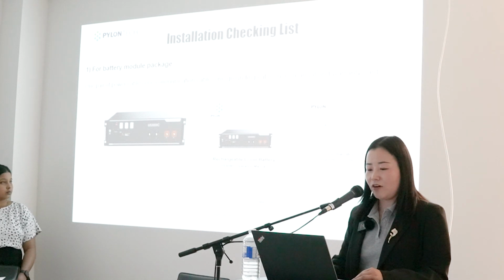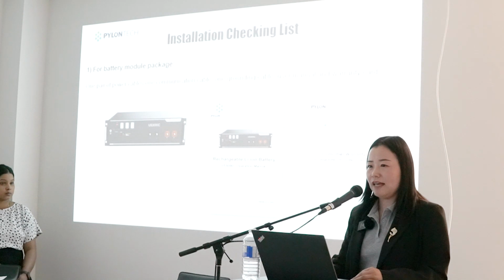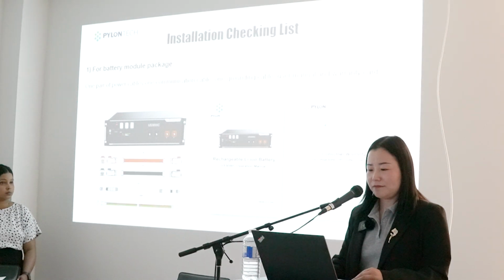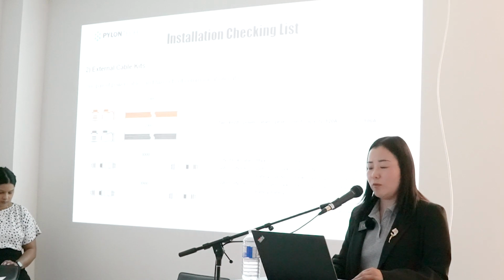So before installation, you have to check the battery module package. For each battery module package, you could receive a pair of power cable and one communication cable to connect between the batteries. Also one grounding cable, user manual, and a warranty card. When you receive the warranty card, it's better if you fill it and submit it to us. And we also have external cable kits. In the external cable kits, there's a pair of power cable to connect the battery to inverters, and two communication cables. One blue mark is to connect the battery to inverter, and another silver mark is for parallel connecting between master batteries.